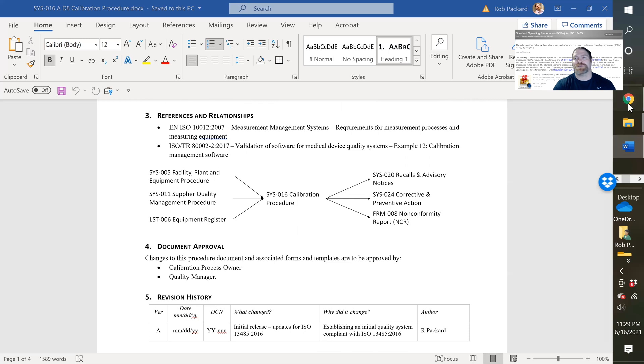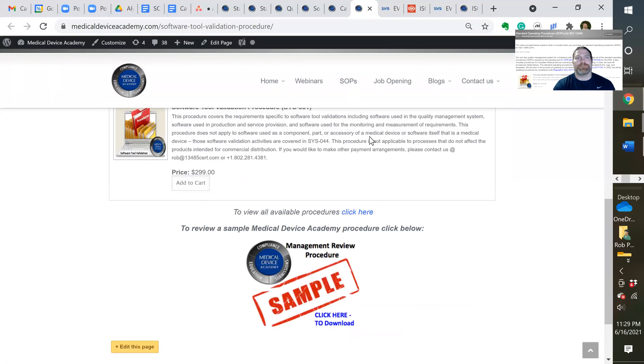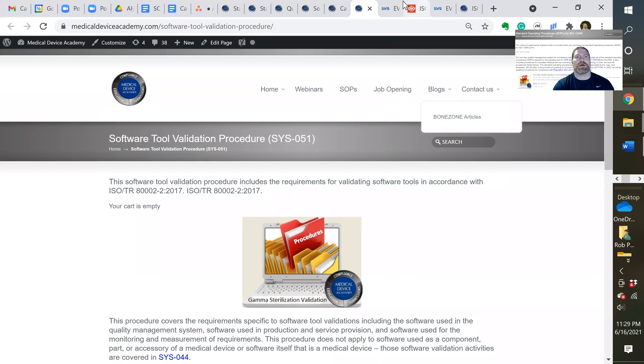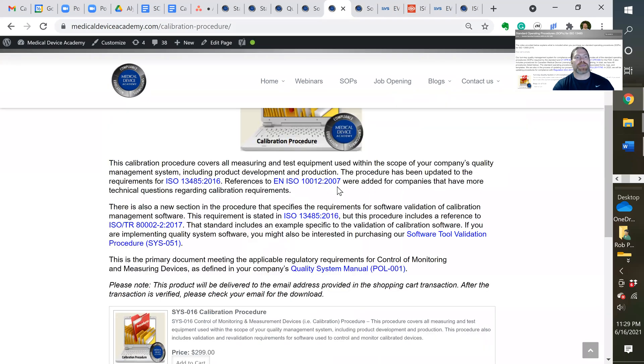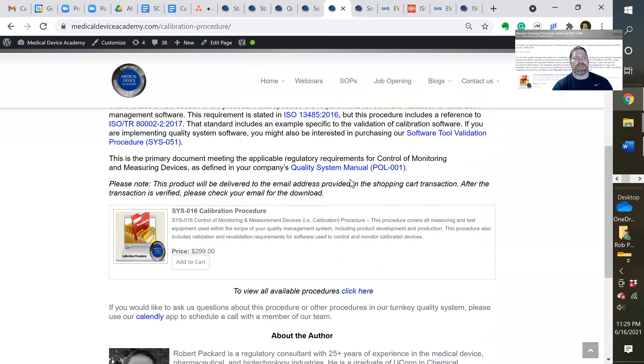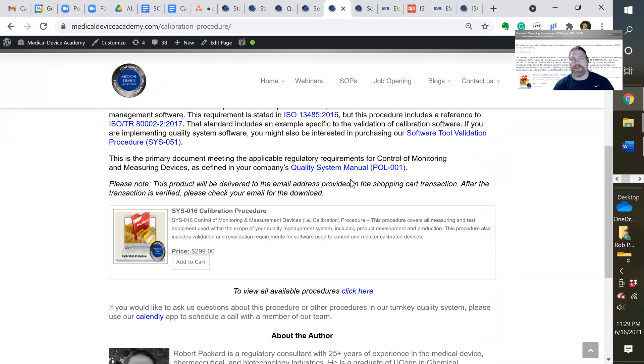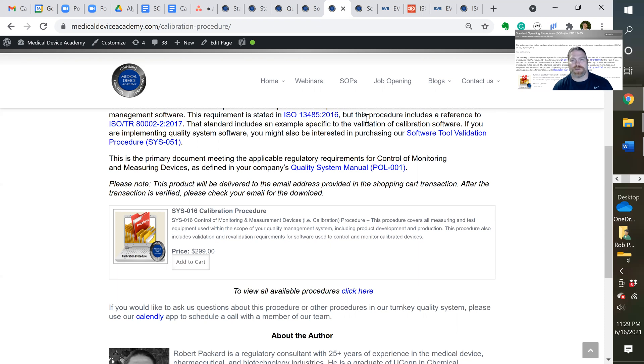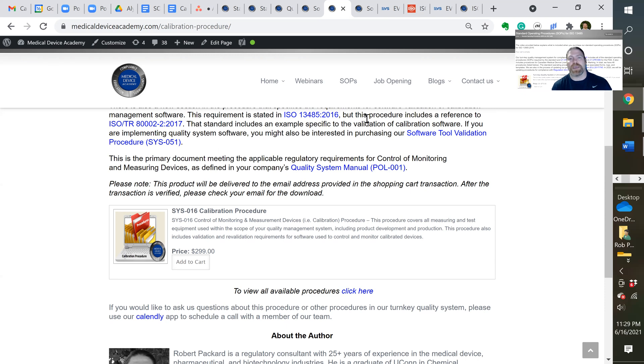One of the questions I get all the time, people will look on the page. Let me go back to the calibration page. They'll look on the page and they'll say, well, it doesn't say anywhere whether this is compliant with the latest version of whatever. So it could be ISO 13485. Well, we say 13485 2016. What about the FDA QSR? Well, the FDA QSR has had very small changes since 1996. So I promise you, it meets the requirements of 21 CFR 820.72 for calibration.